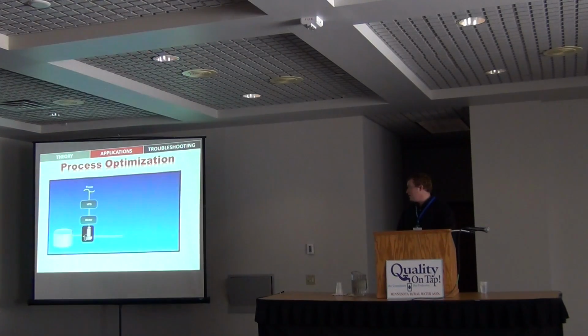So for speed control, what can we do? We have power coming in, it hits your VFD, powers your motor, and that runs a pump. Well, if we have a pressure or flow transmitter on the line, flow meter, magnetic flow meter, or pressure transmitter, we can run that 4 to 20 milliamp signal back into our VFD, and through SCADA or some other external setting, we can provide a pressure and flow setting on the drive and match that. So we can keep a constant pressure, constant flow on the system that might be less than running that motor full speed.